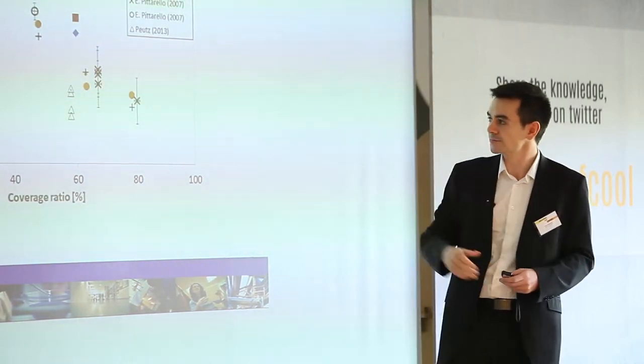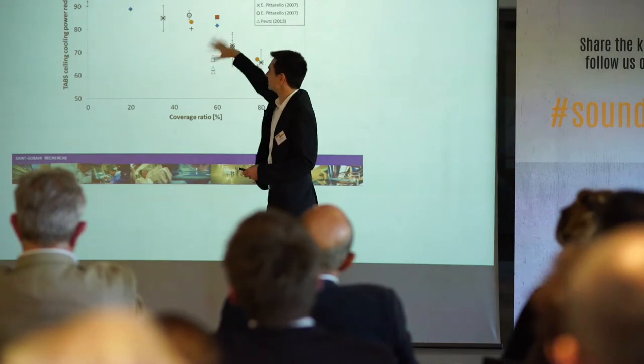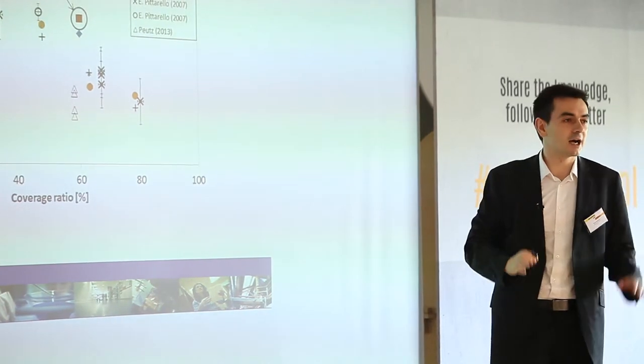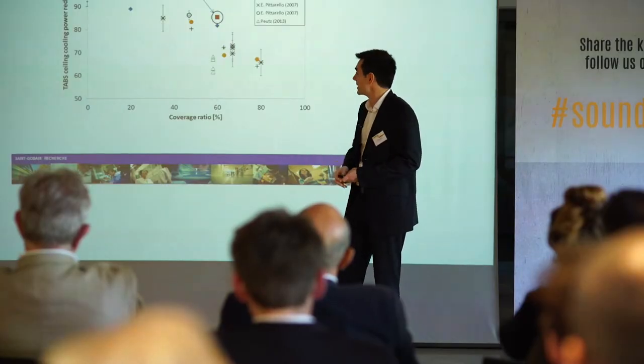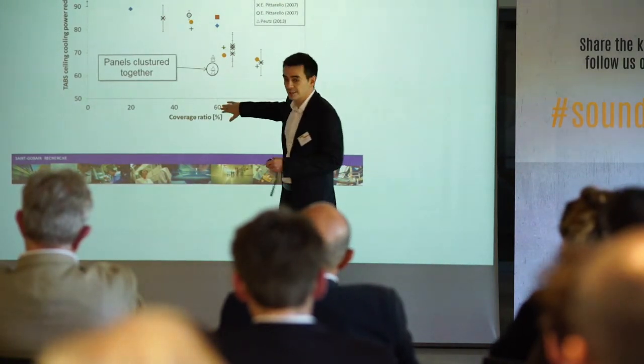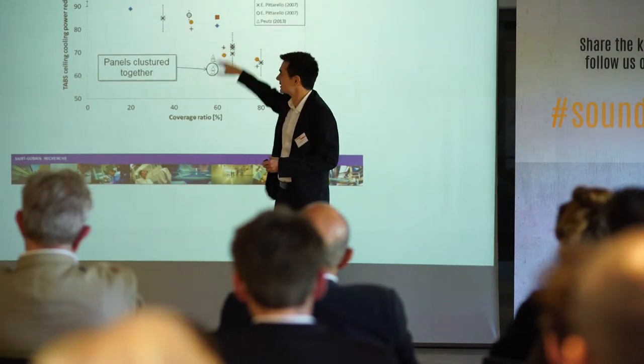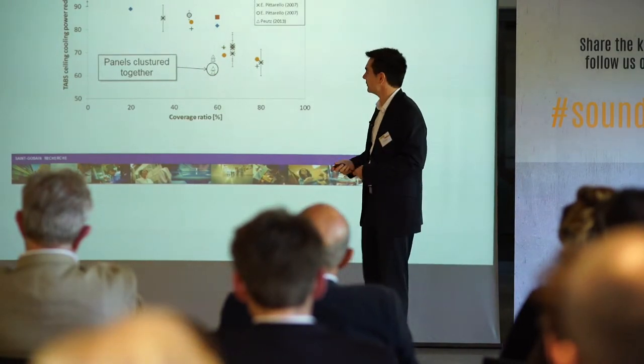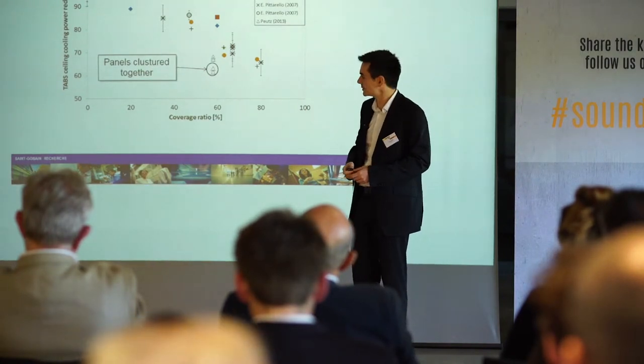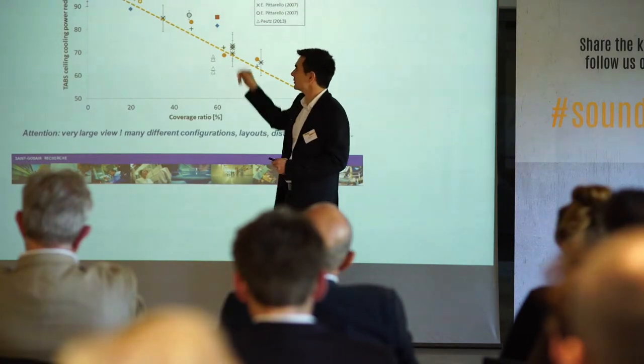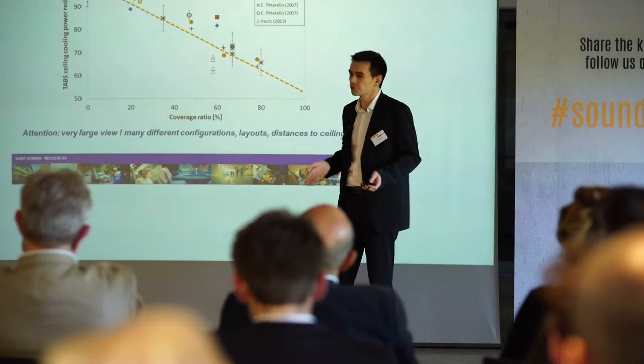On this graph, I put all the data I've read in the papers. We have a lot of points — very interesting. When we look at this, we can make some observations. First, around the value of 60 percent, there is a large spread of values. That's because I plotted all the data I found. For example, in some cases we have panels which are very far from the ceiling — around 80 centimeters — while in other points we have panels clustered together in the center of the ceiling and close to the ceiling. So for the same ceiling coverage ratio, we have two very different effects. If we try to make a linear relation between the two, we obtain a correlation coefficient of 0.87 — not so good, but not so bad either.